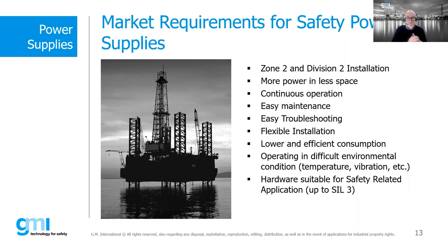Available up to SIL 3, we know that to meet IEC 61508 requirements, instruments must be able to detect or tolerate under voltage and or over voltage conditions, and also maintain the SIL within the normal operating range. These requirements are necessary to avoid dangerous situations and to protect the instrumentation involved in the application. The PSS 1250 is a certified device with both under voltage and over voltage protection.